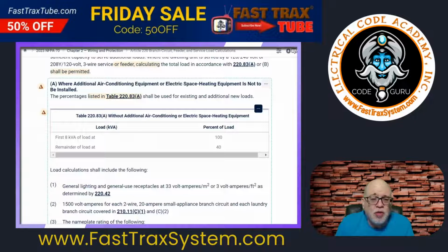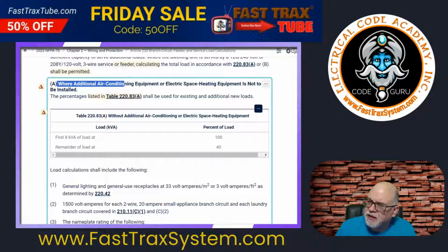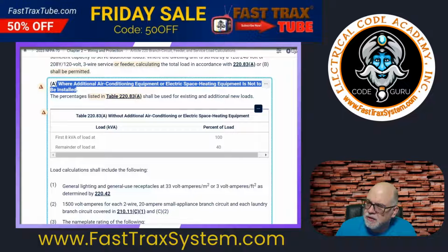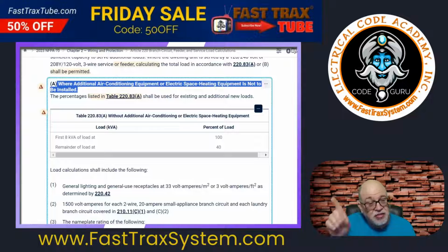If you have loads in the dwelling, you have to account for those. You just can't say, oh, well, there's no nice, nifty place to put these loads, I don't have to account for them. Well, no, you still got to account for them. So if you look at this one, A, it says where additional air conditioning equipment or electric space heating equipment is not to be installed. Notice that it says additional. So if there is existing air conditioning loads or existing electric space heating, you still have to account for those.